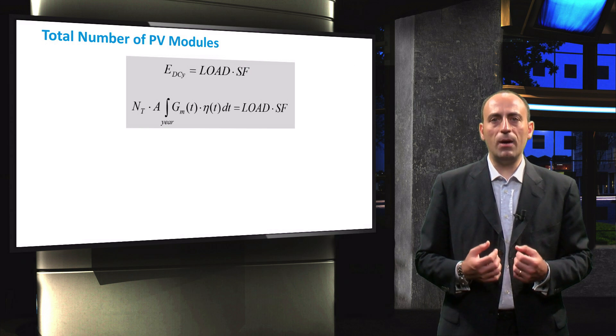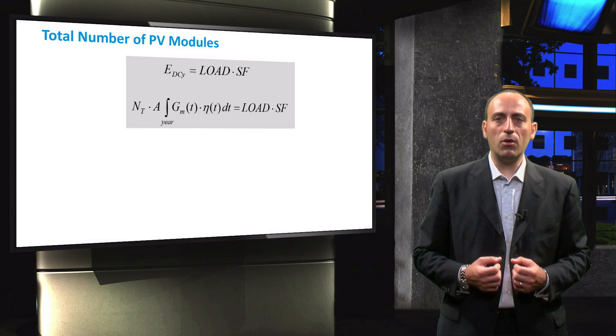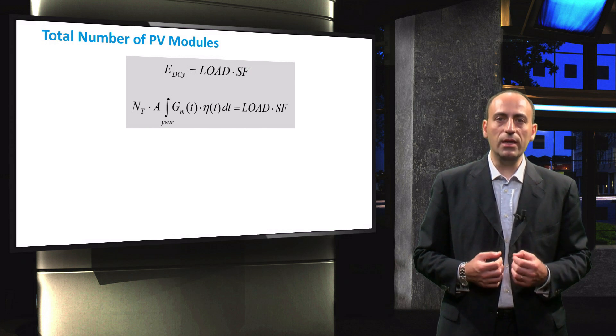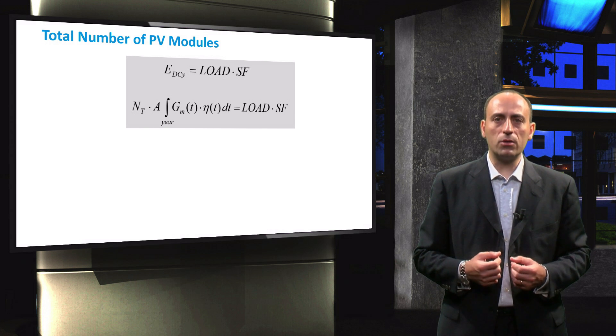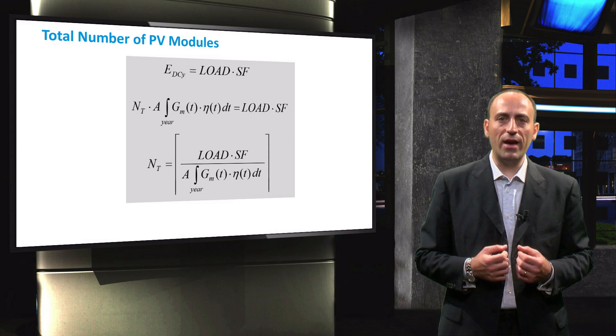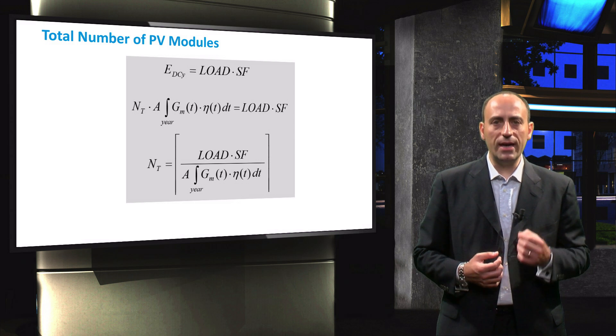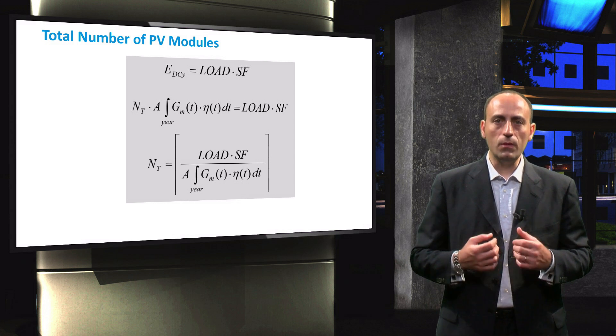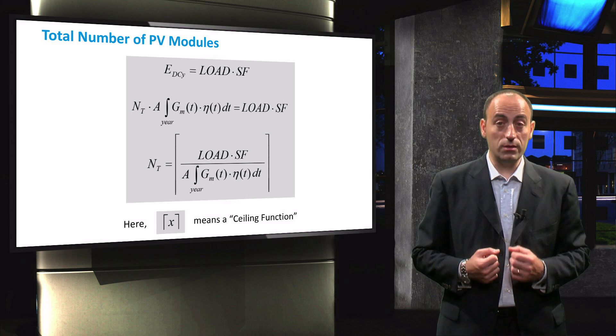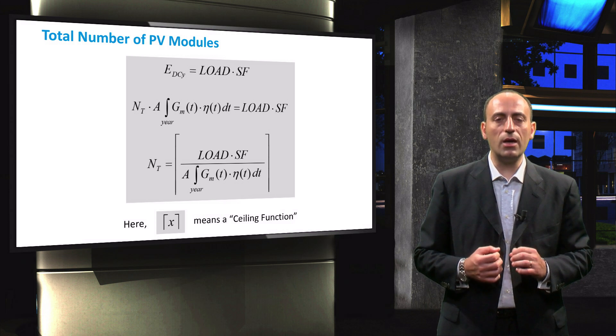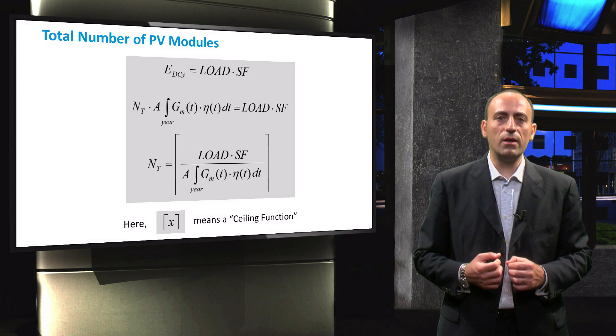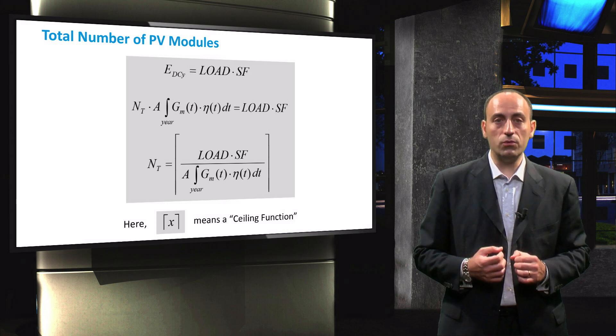With the energy balance in place, the total number of PV modules required, NT, can be calculated. This number is equal to the product of the load demand and the sizing factor divided by the energy generated by a single PV module. Note that the parentheses in this equation denote the required number of modules is rounded up to the nearest integer that is greater than or equal to the x.